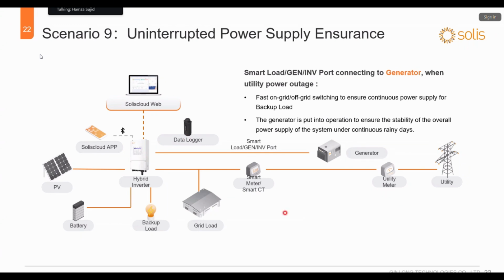If the grid is turned off, PV will support the load. But if the PV is not sufficient for the load, or it is night time, the battery will support the load. Now let's suppose the battery also drops to 50% or any other percentage that you set. Once it reaches the set point of the SOC, it can automatically turn on the generator, which charges the battery and supports the load. Once the batteries are charged again, it will automatically turn off. So the customer doesn't have to turn the generator on or off himself. The inverter itself will automatically do these tasks.